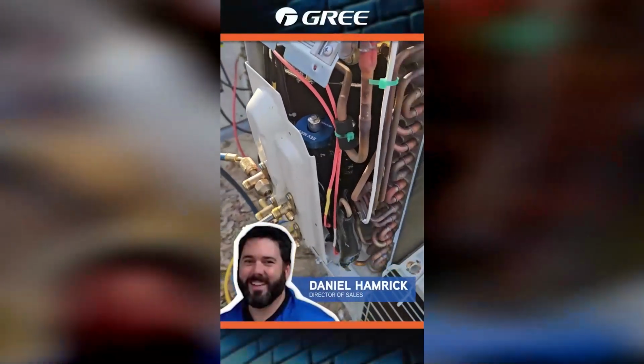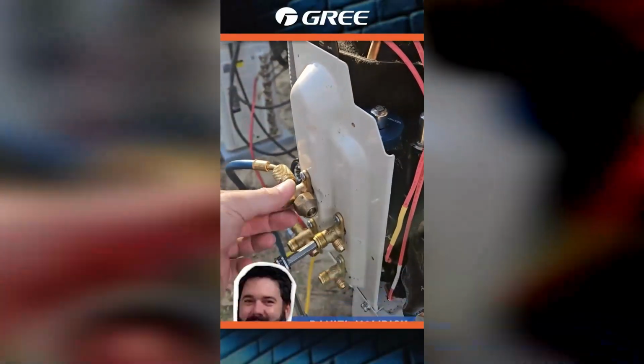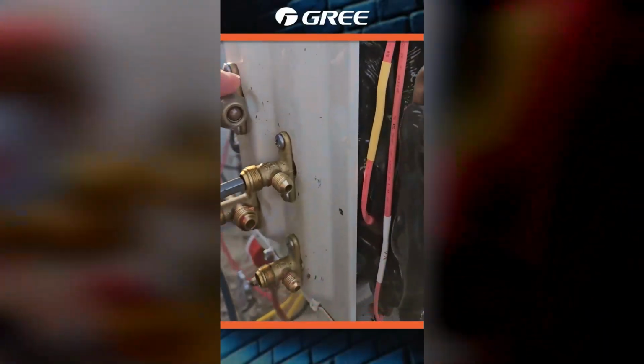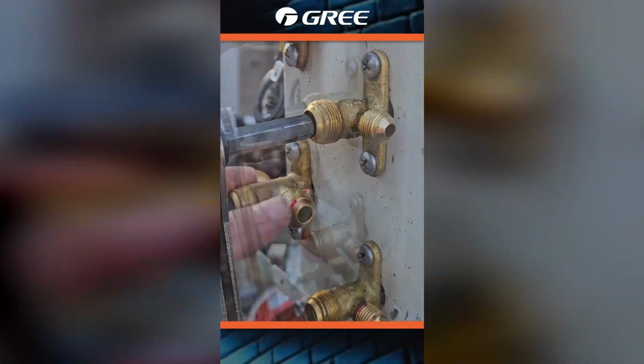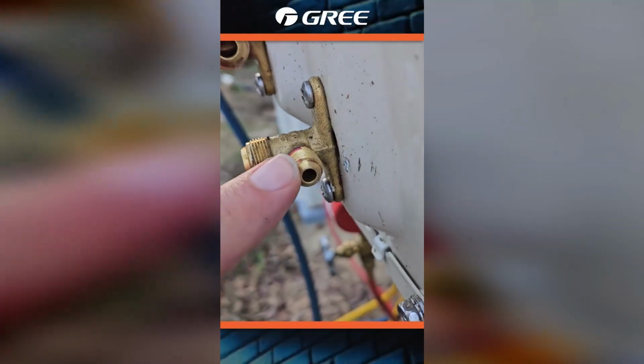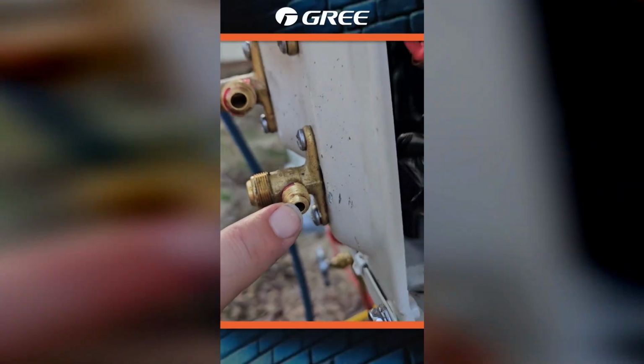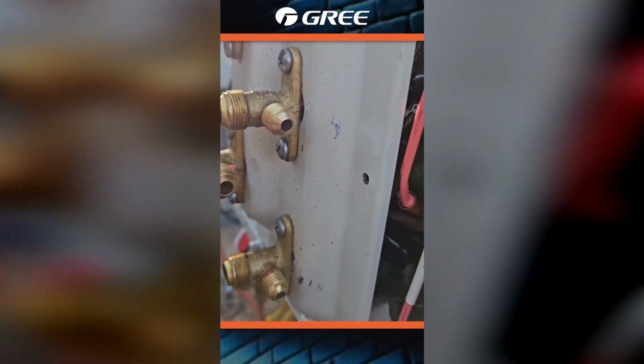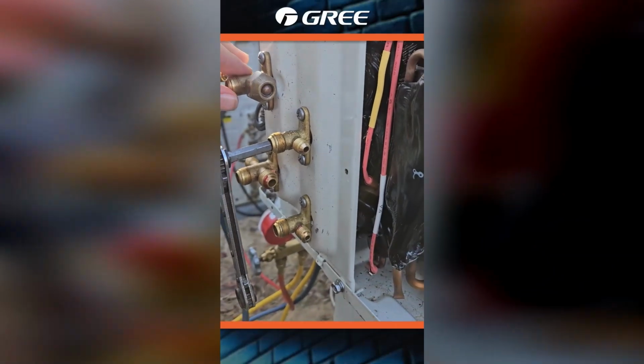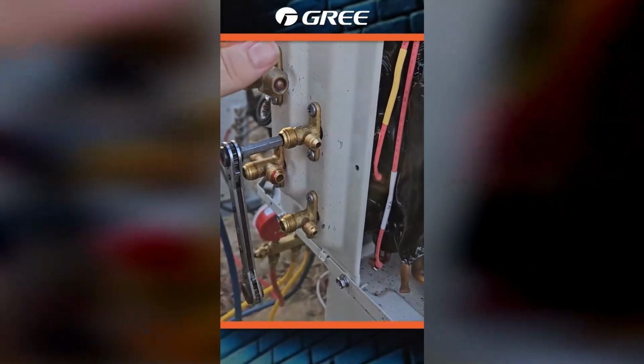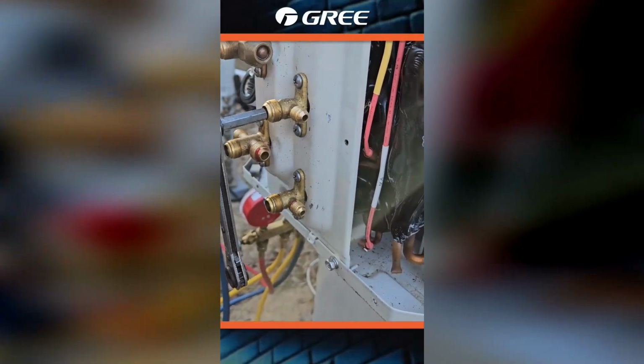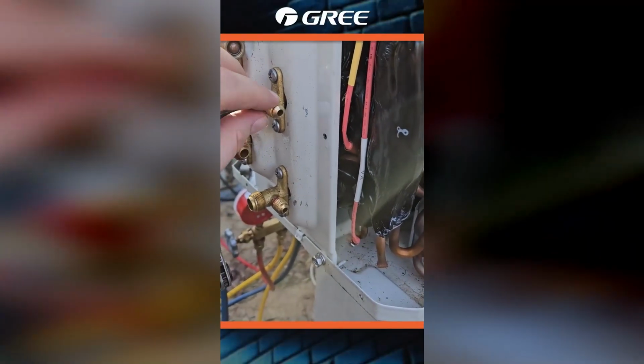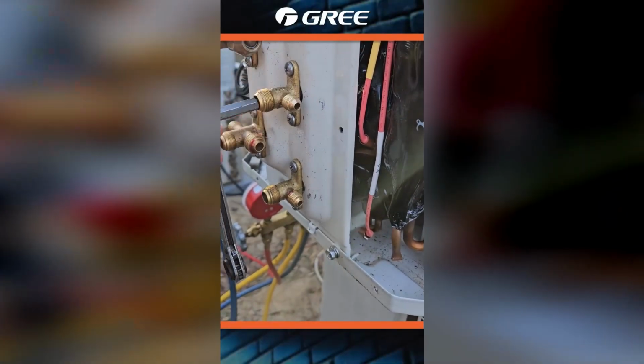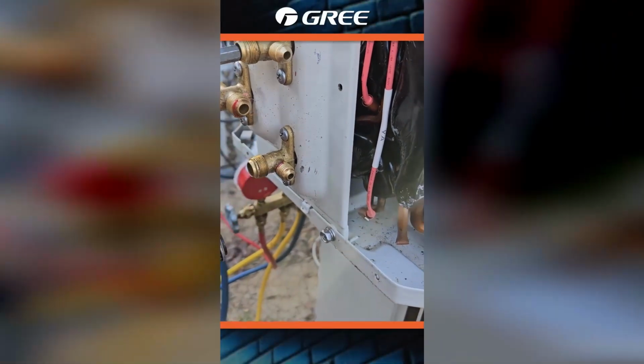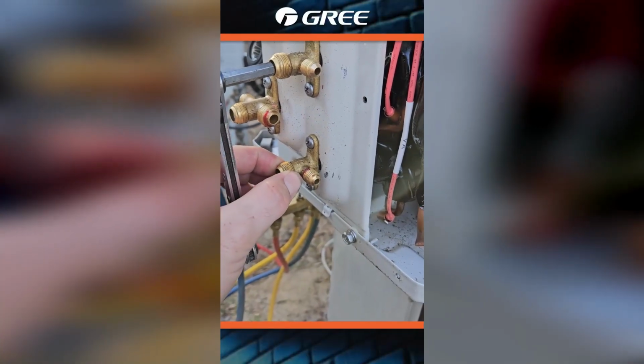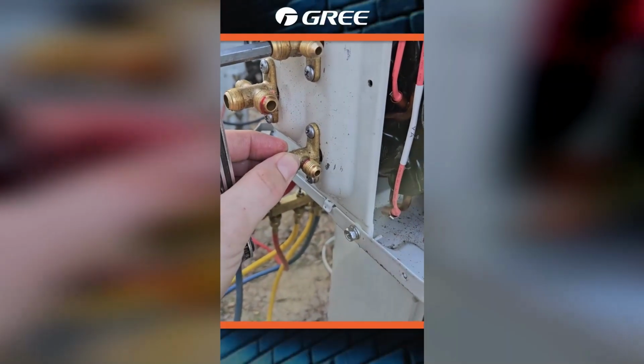Doing a little troubleshooting with the EEV Mag. What I noticed was there is Loctite on these threads. Taking a look at this one in particular, there was some inside, which I scraped out and blew out a little bit just for test purposes. I put about 100 psi pressure on the outdoor unit by itself. I shut these valves off, and then I cracked this one open. I did get some pressure out of it, and this is a 1/4 inch port. So I cracked this one open and nothing's happening.